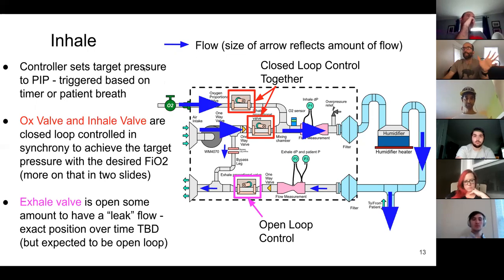So for inhale, what's happening? We need to increase the patient pressure, so we do that by increasing the flow of gases. Right now, with the split of oxygen from air, which we'll talk about later, both of those valves are essentially going to move together, and those are closed loop control on pressure.